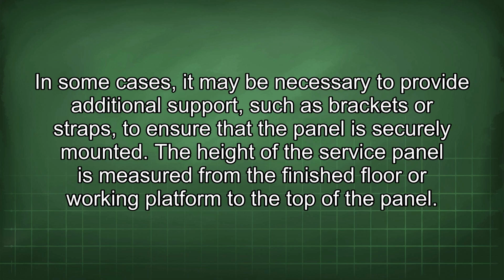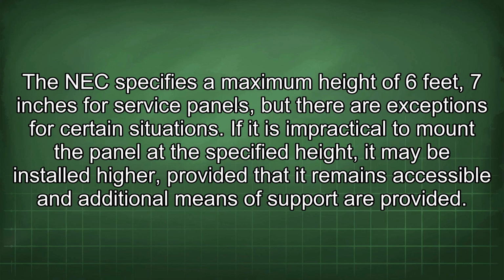The height of the service panel is measured from the finished floor or working platform to the top of the panel. The NEC specifies a maximum height of 6 feet 7 inches for service panels, but there are exceptions for certain situations. If it is impractical to mount the panel at the specified height, it may be installed higher, provided that it remains accessible and additional means of support are provided.